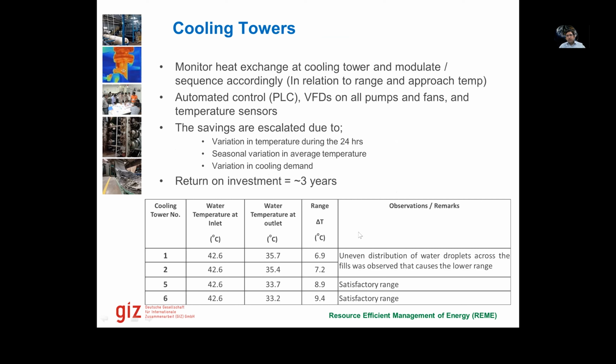Then cooling towers. There we need to monitor the heat exchange that is being done in the cooling tower, how much range we are getting, that is the delta T it is producing, what temperature water is entering the cooling tower and what temperature is going out. Then if we can do an automated control based on temperature sensors, that actually brings in a lot of savings, because the temperature varies the whole day during 24 hours. It also varies among the seasons, and also there is a lot of variation in the cooling demand.